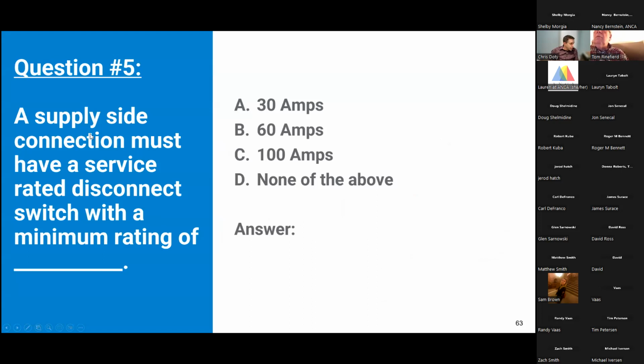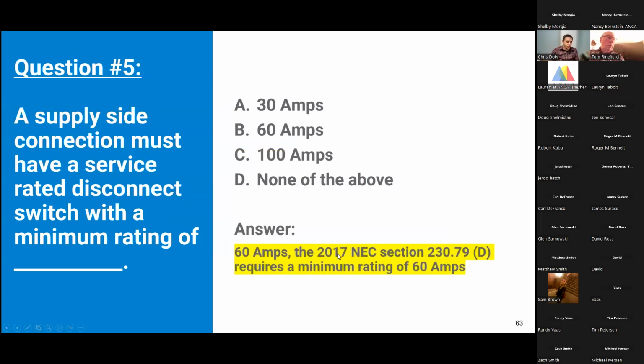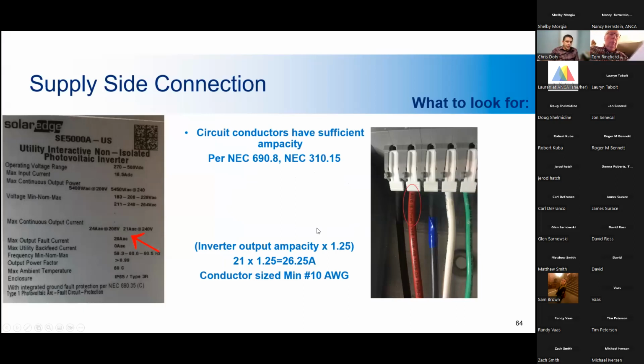All right, and this is one that we should be able to get fairly easily, since I literally just said it. A supply side connection must have a service rated disconnect switch with a minimum rating of 30, 60, or 100 amps, or none of the above. You can put that in the chat. We're a little bit over halfway through, but we should be able to move a little quicker soon here. So we'll keep going. The correct answer is 60 amps, which we just talked about.